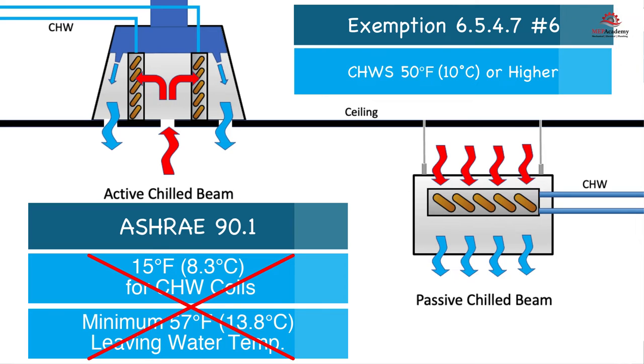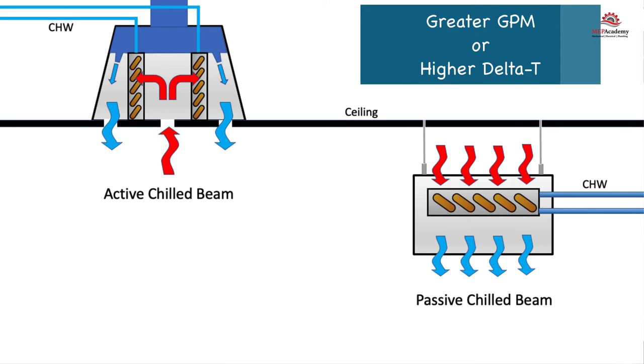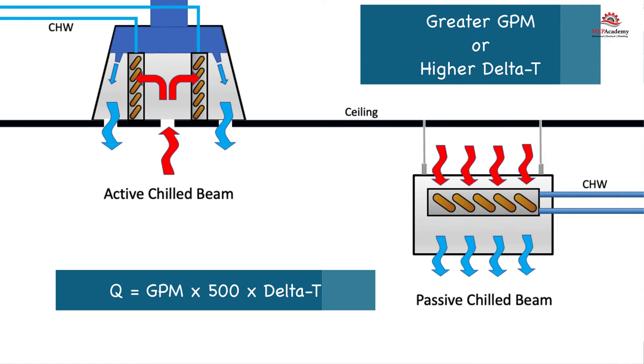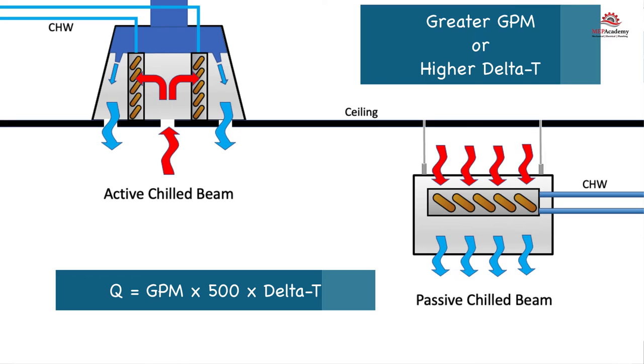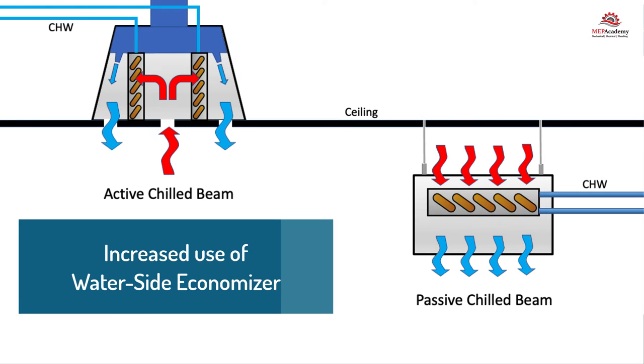In order to achieve a larger capacity chilled beam, you need either greater water flow or a higher delta T, as the equation is Q = GPM × 500 × delta T. By increasing flow or the delta T, you can increase the capacity. However, chilled beams are limited by their size and the temperature at which chilled water can be delivered to avoid condensation. With an increase in chilled water supply temperature, there will be an increase in the duration for which a waterside economizer could be used.